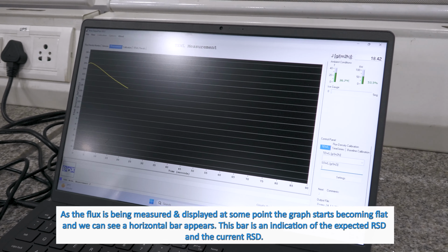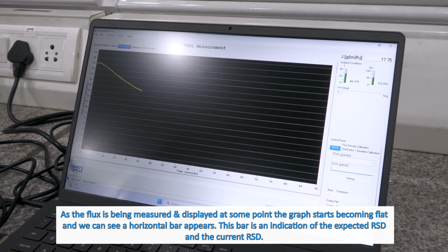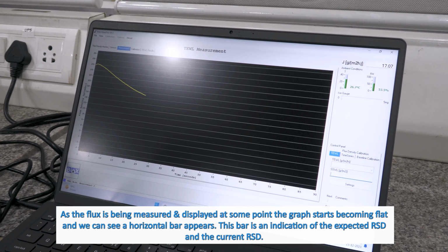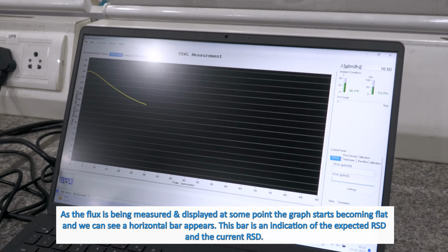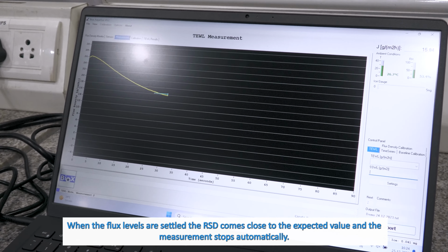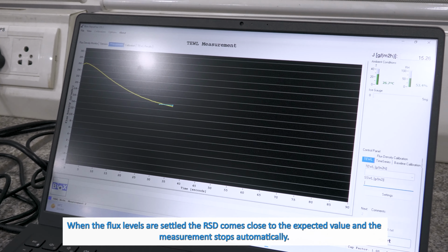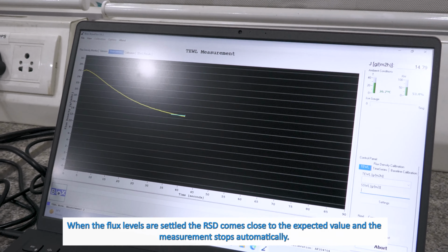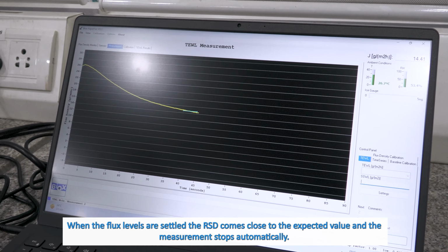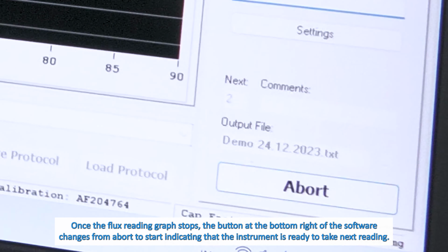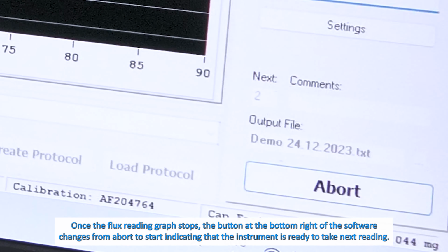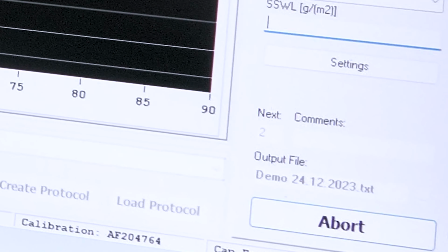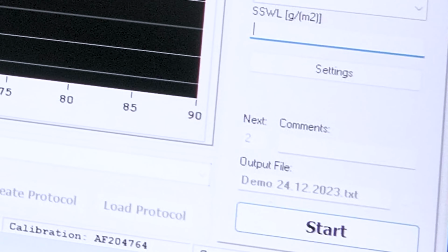As the flux is being measured, at some point the graph starts becoming flat and a horizontal bar appears. This bar is an indication of the expected RSD and the current RSD. When the flux levels are settled, the RSD comes close to the expected value and the measurement stops automatically. Once the flux reading graph stops, the button at the bottom right of the software changes from abort to start, indicating that the instrument is ready to take the next reading.